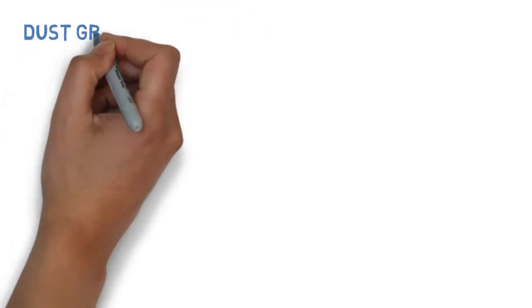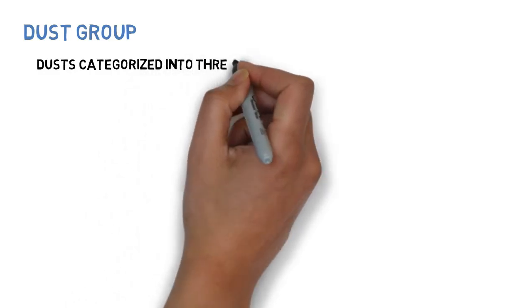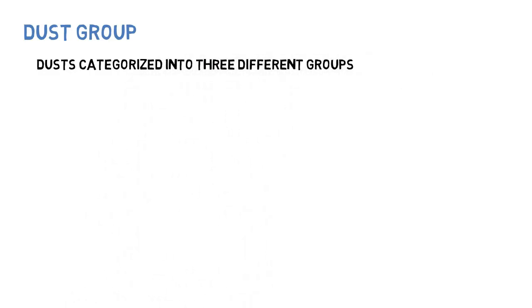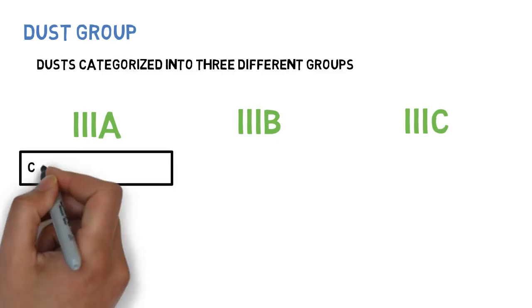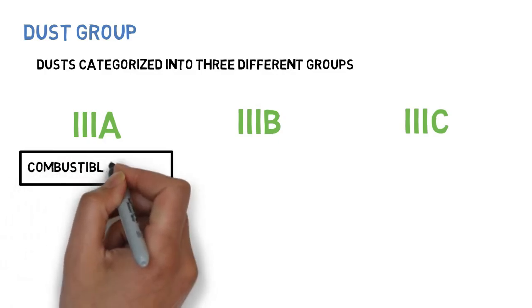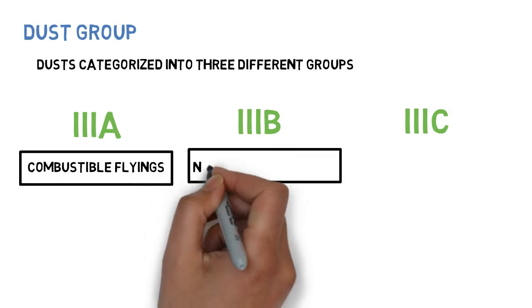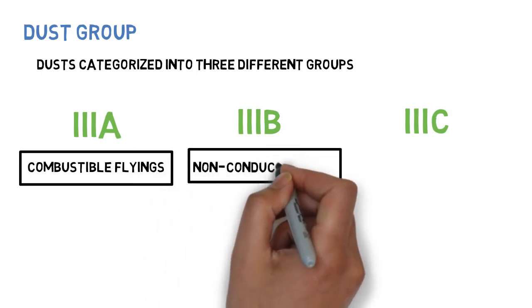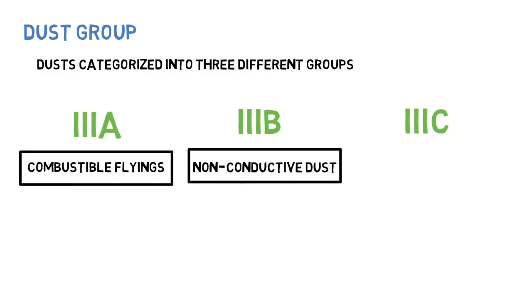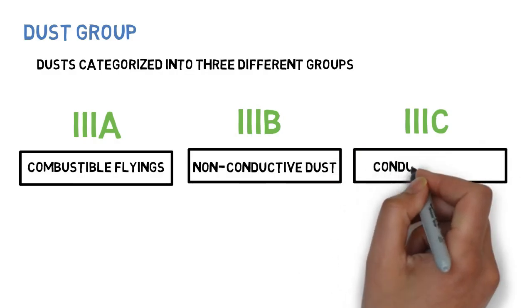Dust group. Dusts are categorized into three different groups: 3A, 3B, and 3C. 3A is for combustible flyings, 3B is for non-conductive dust, and 3C is for conductive dust.